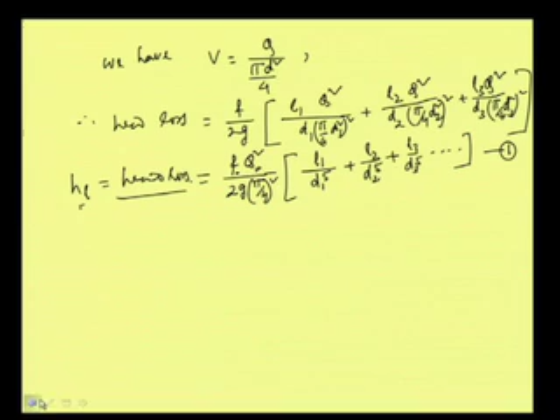Because this is the equivalent, this head loss is equivalent to this particular head loss. So, what we can write, equating 1 and 2, because this head loss is the same: fL Q square by 2g (pi/4) square, then D to the power 5, is equal to, now we can write this part. That part will remain the same, but inside will be changing. That part is f Q square by 2g (pi/4) square, which will be the same. Then we will have L1 by D1 to the power 5 plus L2 by D2 to the power 5 plus L3 by D3 to the power 5, and of course, if there are more in series, then it will continue. Now, we can see that this part and that part is the same.